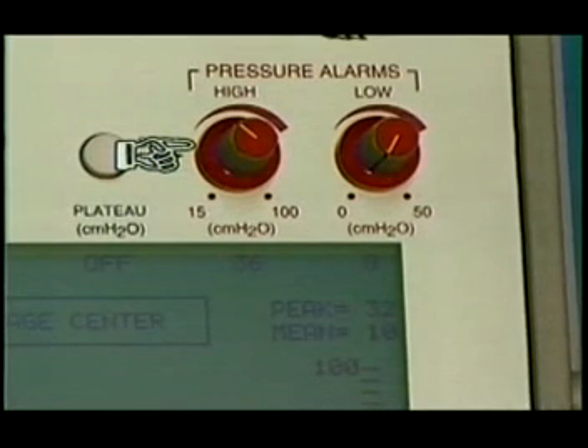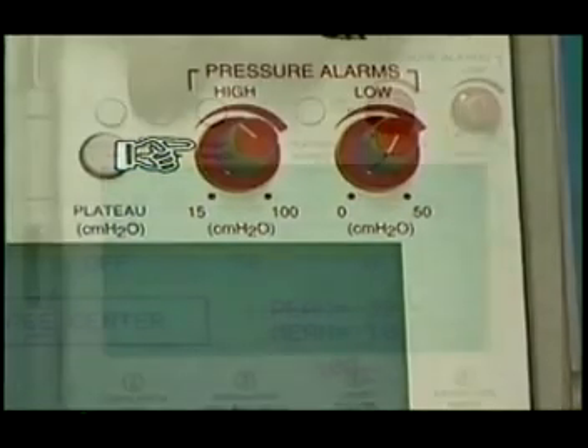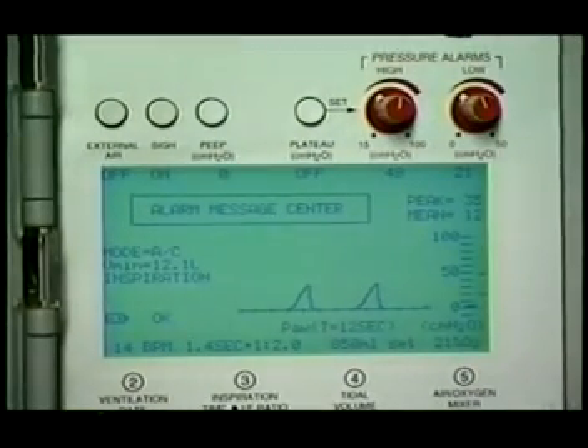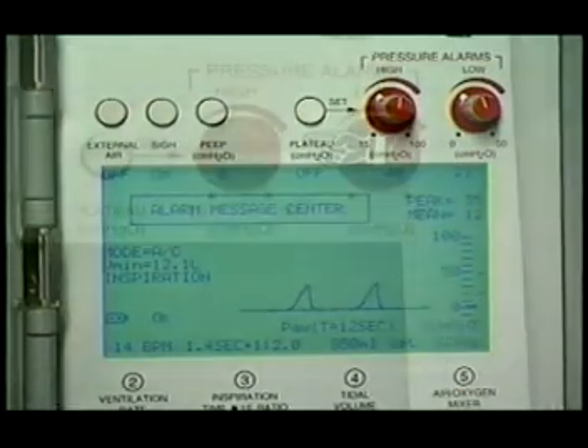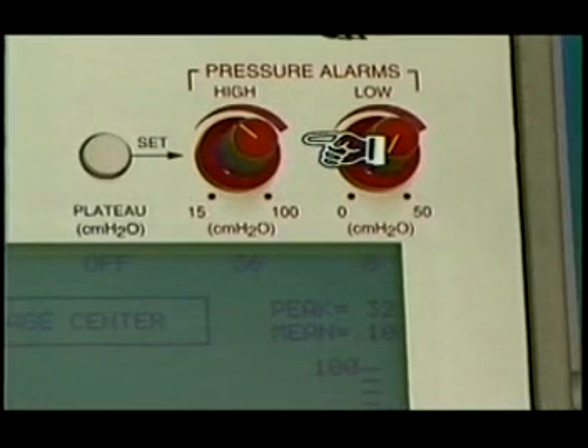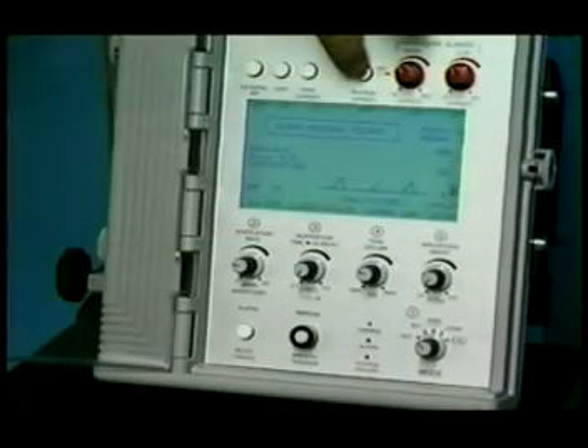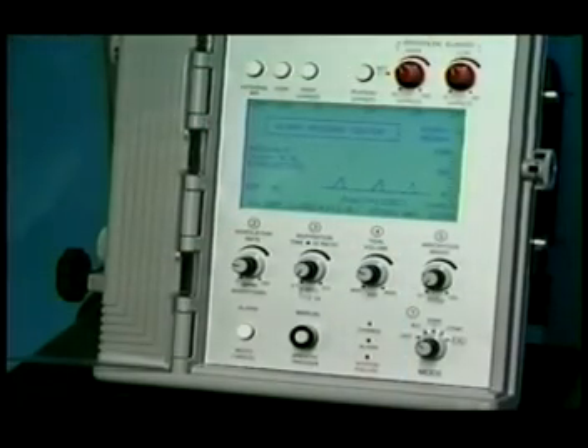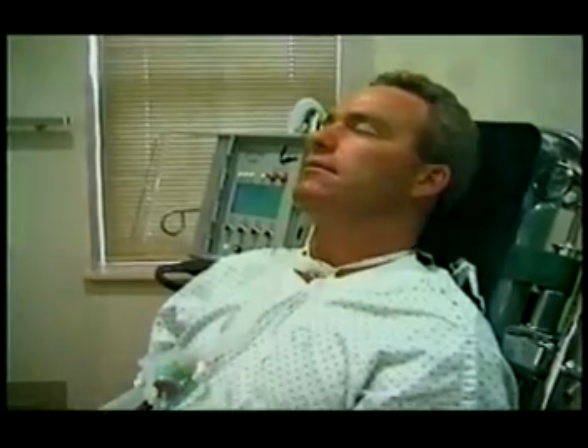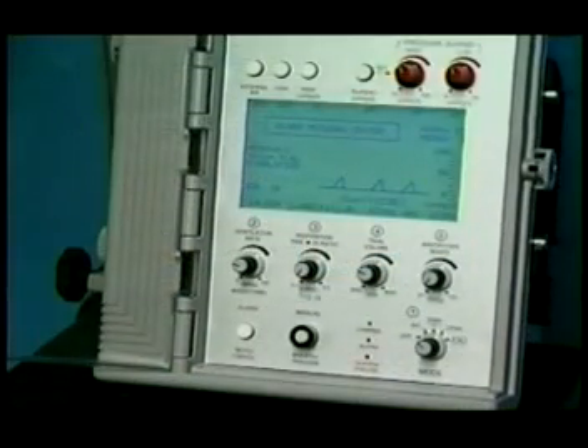Conversely, if you set the high pressure alarm set point to a higher value and then press sigh off and then back on again, a greater volume is delivered because peak inspiratory pressure relief does not occur. Pressure plateau is automatically referenced to the high pressure peak inspiratory pressure relief control set point. Pressing the push button sets plateau to on and establishes a pressure plateau that is always 10 centimeters of water less than the high pressure alarm control set point. In this case, pressing plateau on has no effect because the peak airway pressure is only 26 or 27 centimeters of water, which is less than the plateau value.